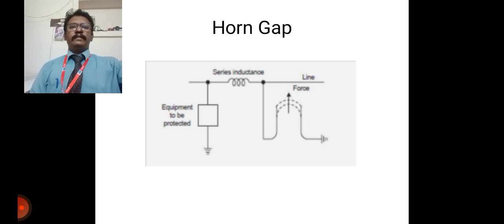Next, you can see here, whenever a surge voltage exceeds the breakdown value of a gap, a discharge takes place, and the energy content in the rest of the wave is bypassed to the ground. An arc is set up between the gap, which acts like a flexible conductor and rises upward under the influence of the electromagnetic forces, which normally happens in the diverters. Thus, the length of the arc increases, and it eventually blows out and won't sustain.